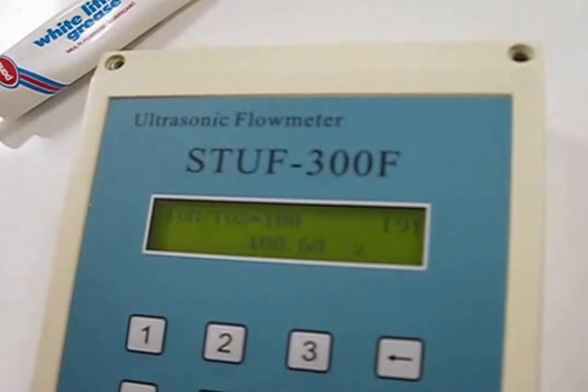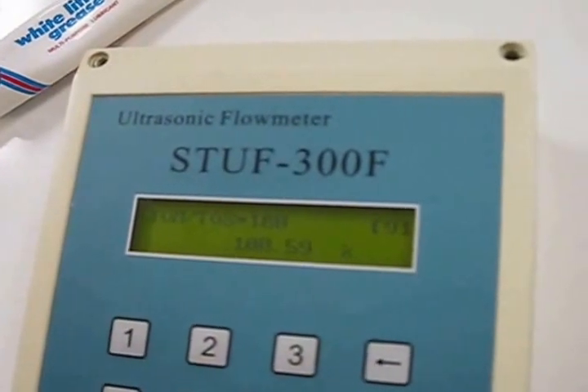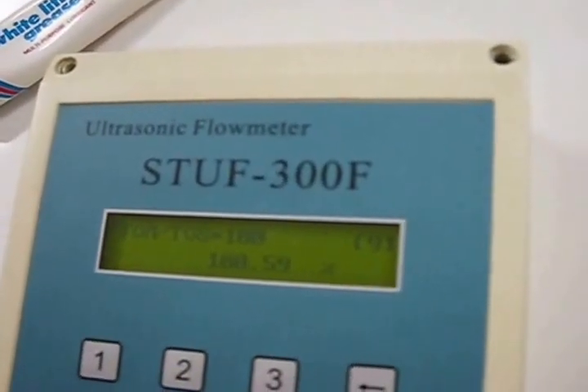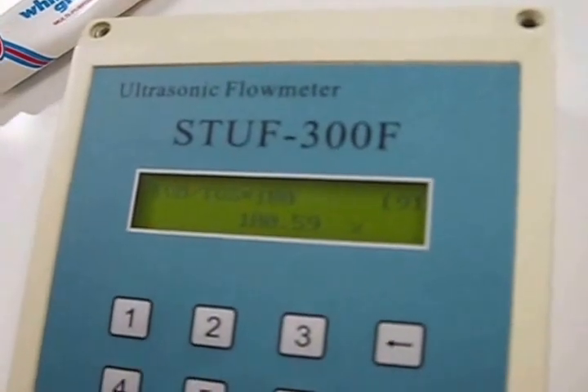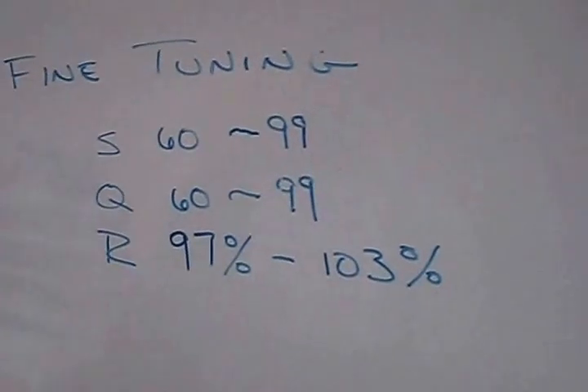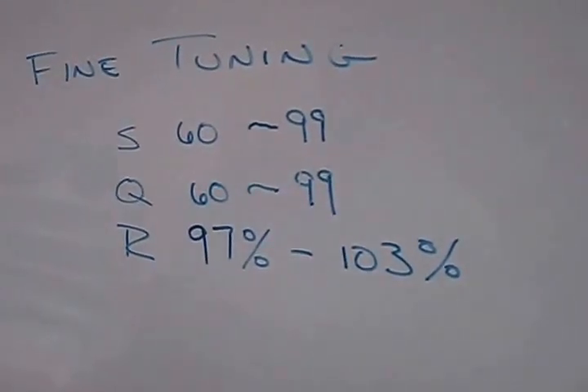We go to menu 91. Menu 91 displays transit time ratio. Our transit time ratio for this flow meter is 100.59. It is within the parameters of 97% and 103% that we need for a correct reading.